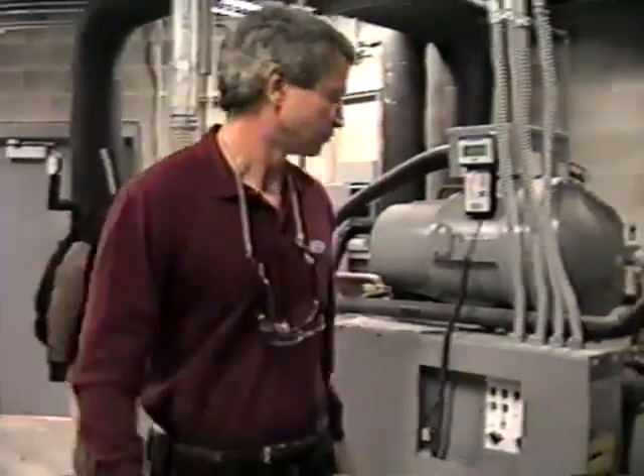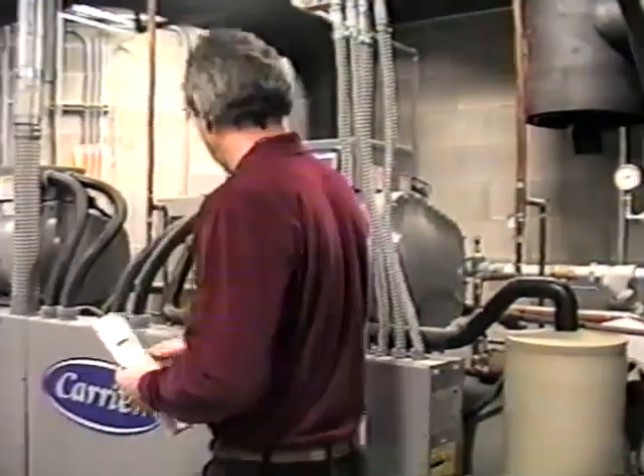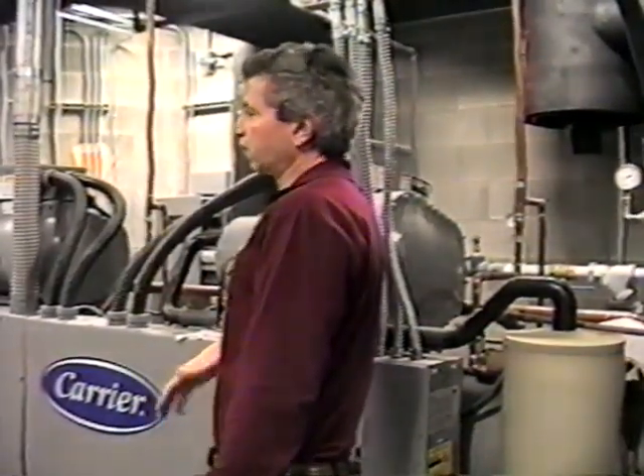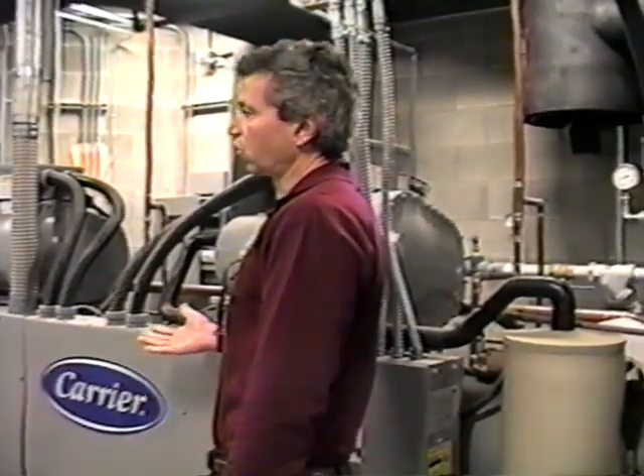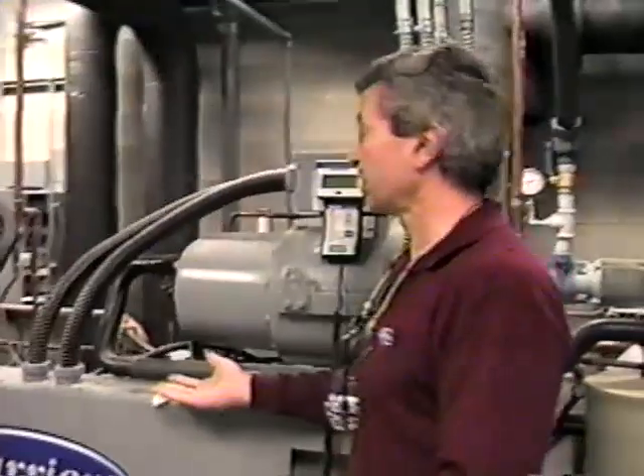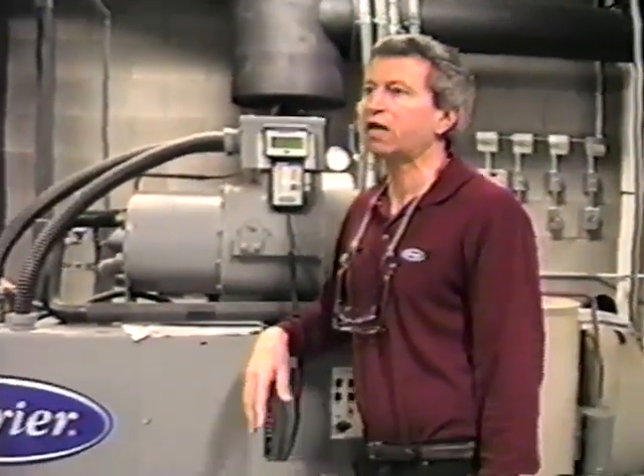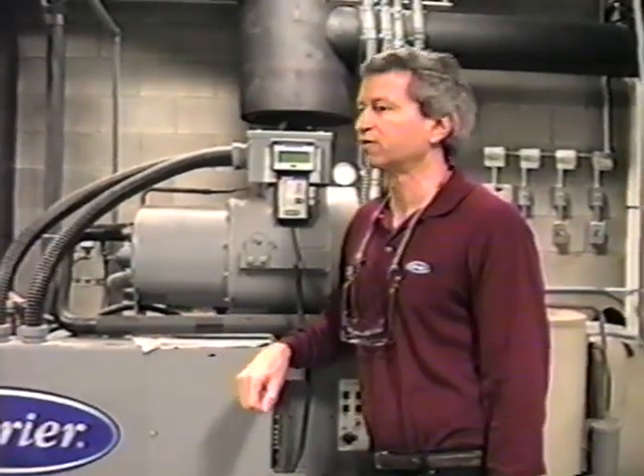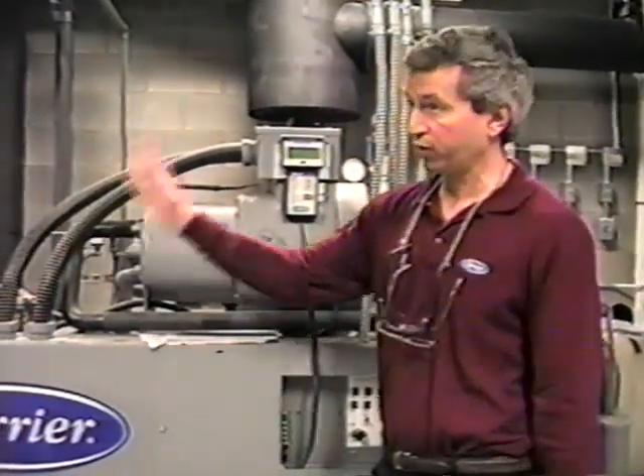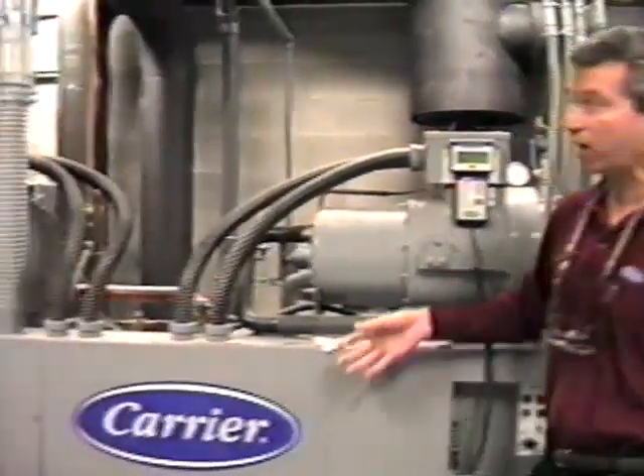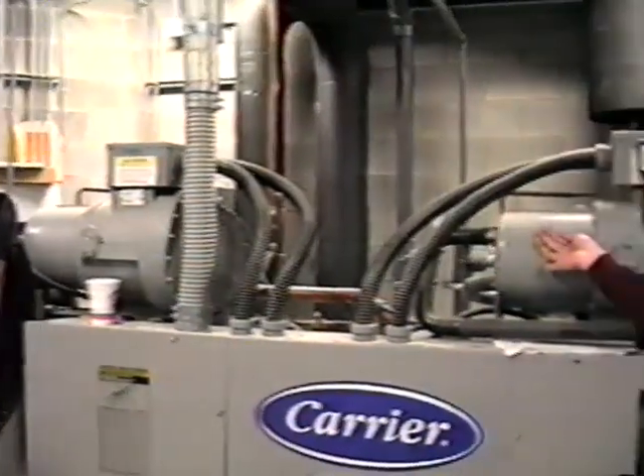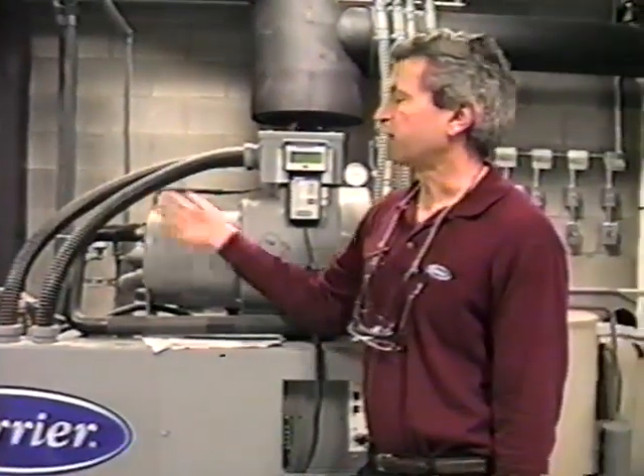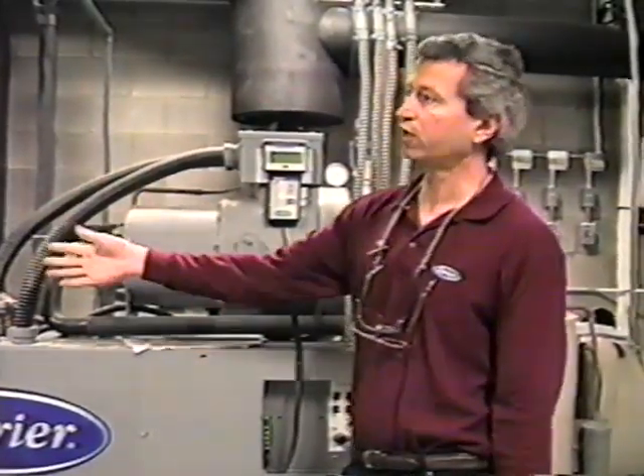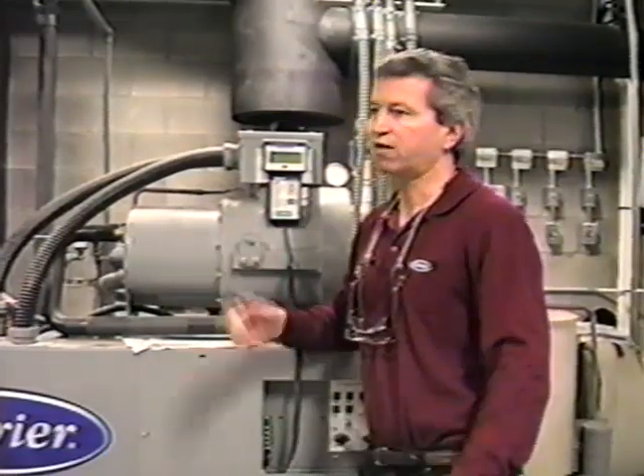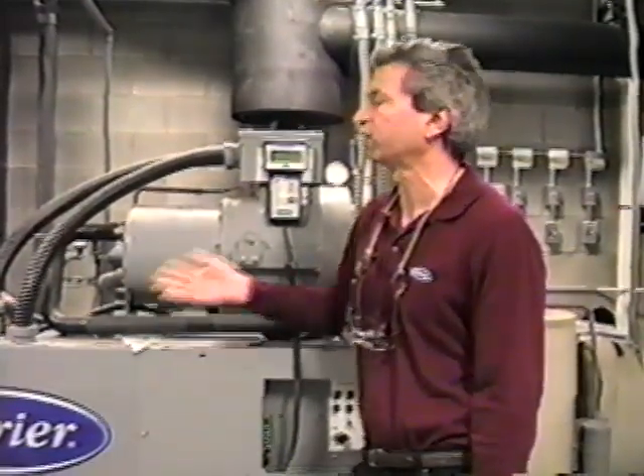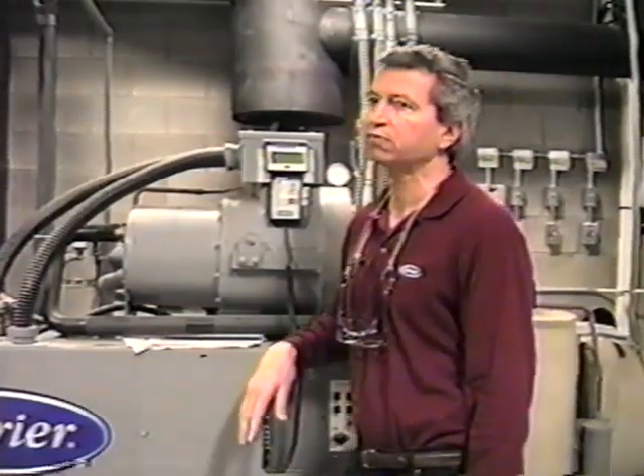Just a general overview of what the machine consists of. Like I said, it's a 171 model number. Essentially, it's normally a nominal 140 tons. Because of the temperatures you're running, it's approximately 90 tons in that range, actual capacity output. There are two separate refrigeration circuits on this machine. So you could have a problem with one circuit and conceivably still have a healthy circuit operating. It's about a 55-45 capacity split, so one circuit is a little bit larger than the other. Not enough to matter in your application, because probably either one, once you're down to temperature, will maintain the ring, I would guess anyway.